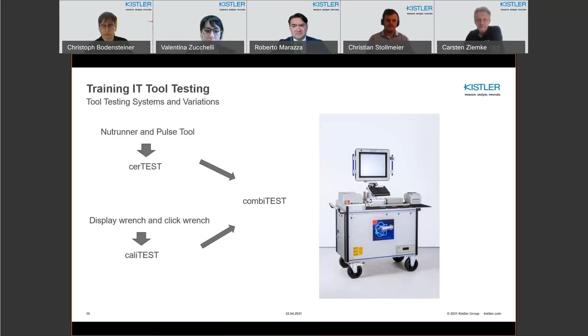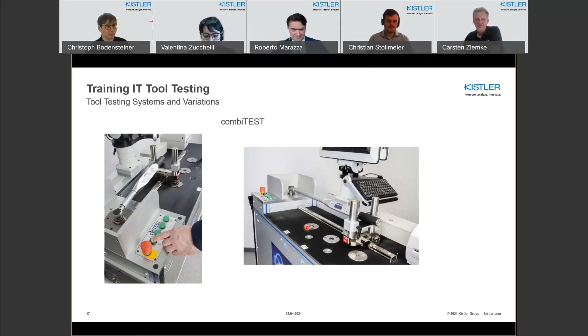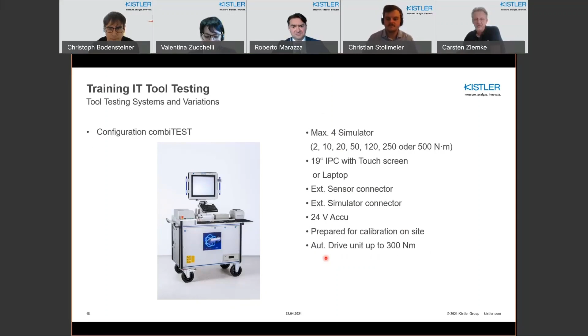You see it here, the drive unit of the caliTEST, the reaction bar, and you have to make sure the tool is in a horizontal position, and then you get the information. You can push the start button, and the system makes this calibration automatically. In front of this, you see the 4 built-in simulators for testing the nut runners. In this case, we also have the possibility to build in 4 simulators, the industrial PC or the laptop support, external connectors, and a 24-volt battery for moving in the production line and working without the main power. And in this case, the standard is up to 300 Newton meter for the automatic drive unit to calibrate the wrenches.